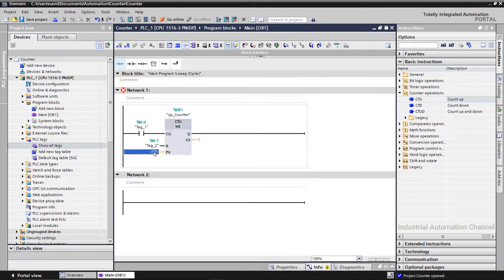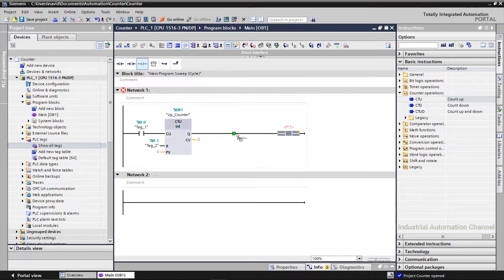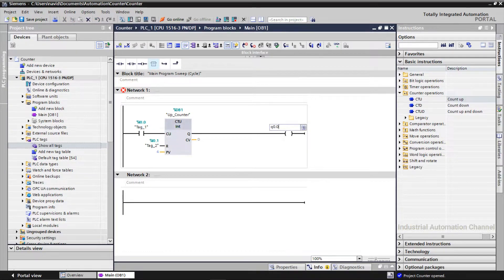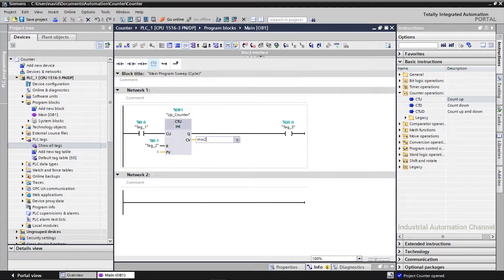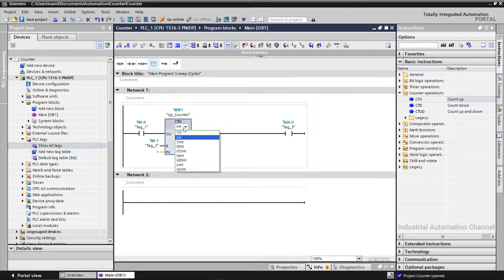I give PV a value of 4. If the current value is greater than or equal to the value of PV, the Q output will be on. I'm going to put an output here. To show which value the counter currently has, it's an integer value so I use a word. By default the format of numbers is integer, but here you can change the number format.